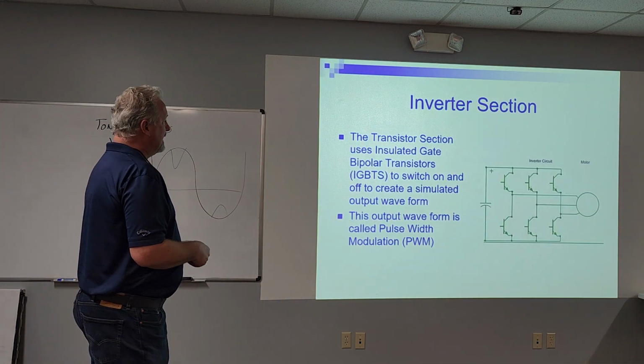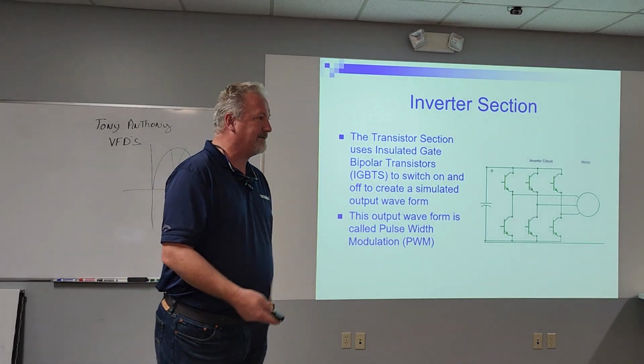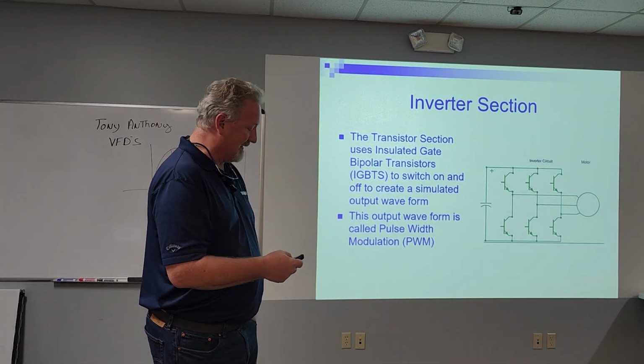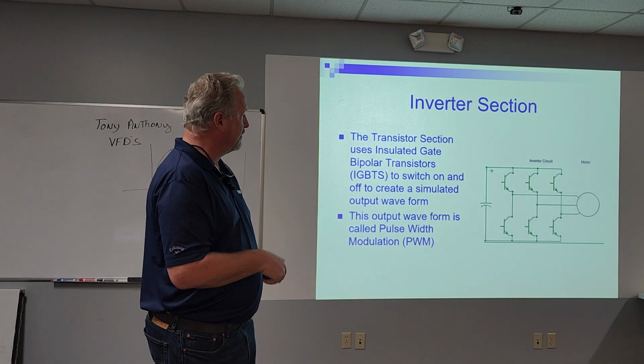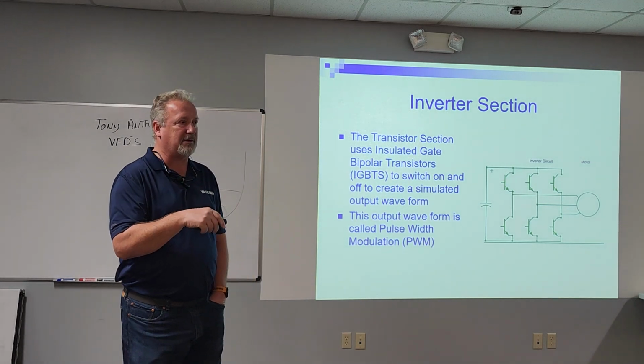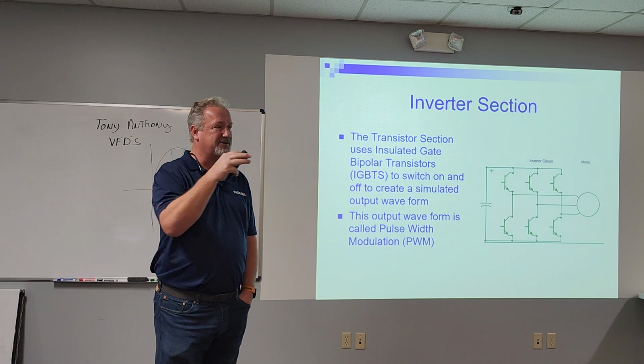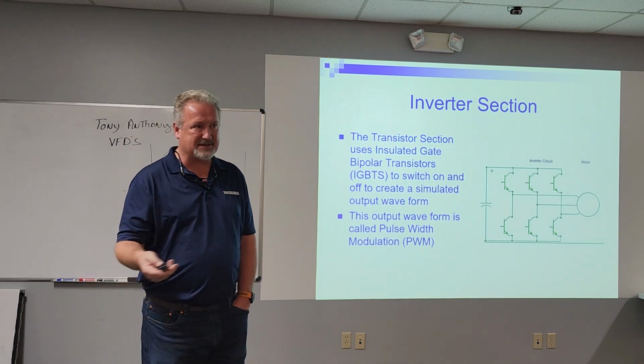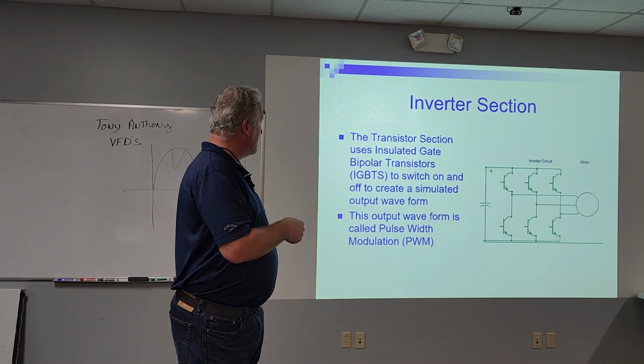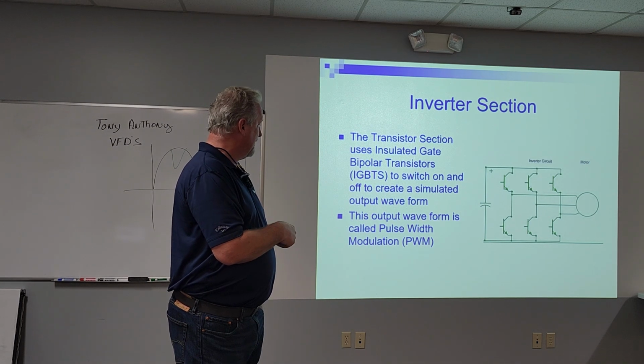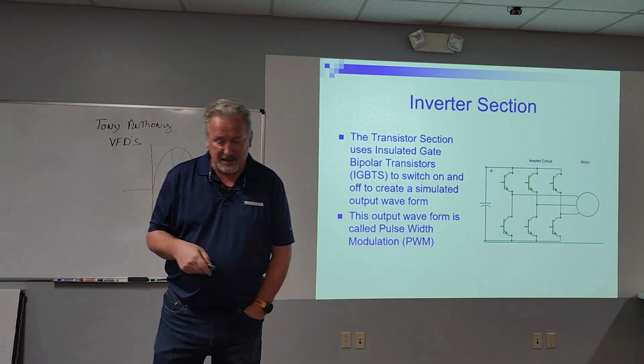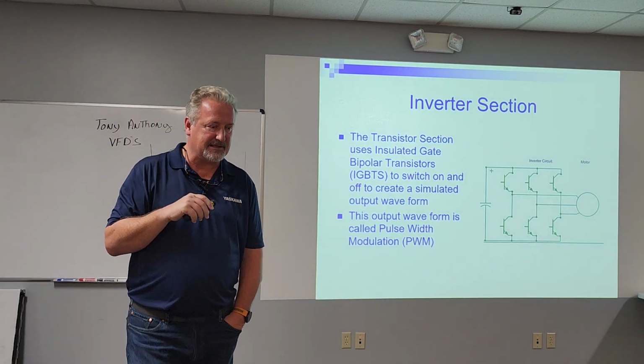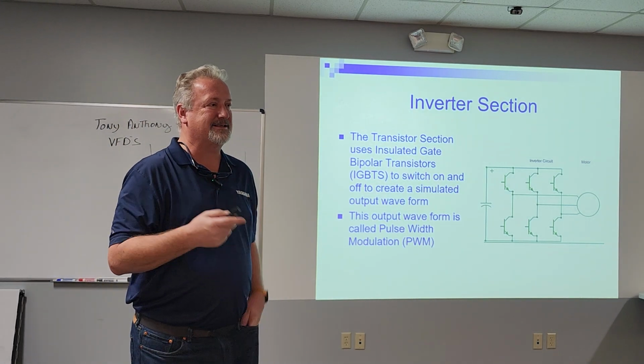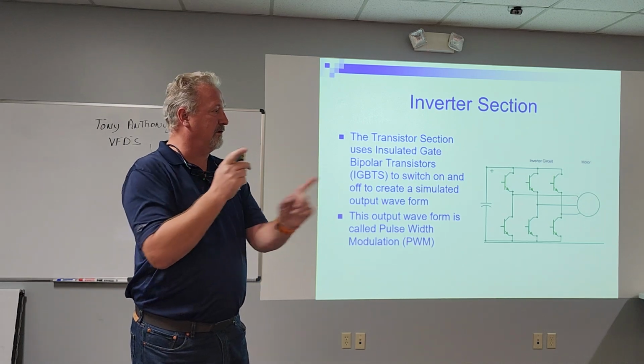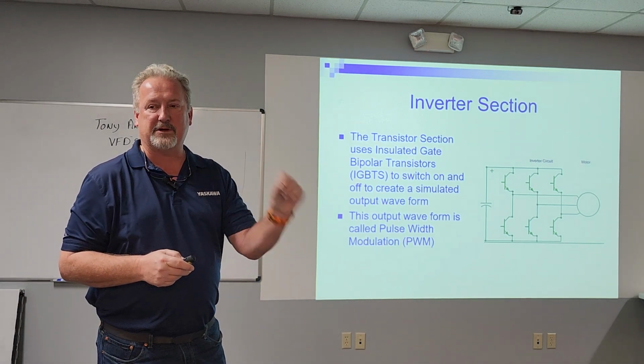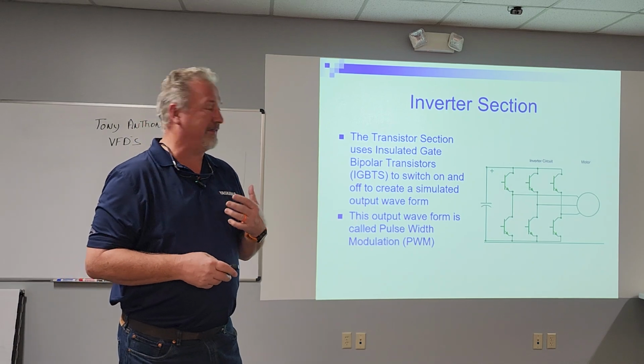The inverter section in most 6-pulse drives, this is every drive out there, we have six IGBTs that are going to fire at different times to create what we call pulse width modulation. Everybody's heard of a PWM drive? That's every drive that's out there for the most part. They use insulated gate bipolar transistors to switch on and off, and they create the PWM. So an IGBT is basically a fancy diode that still controls flow one way or the other, but we can turn it on and off at will as we want to allow that flow.